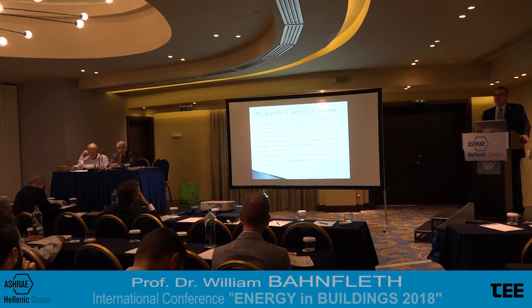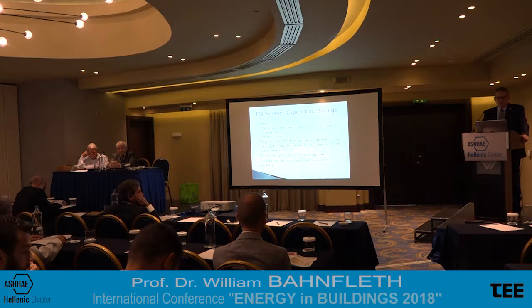On the other hand, that trades off with the cost of the thermal storage component, so I can't tell you that you can always save money with a thermal storage system compared to a non-storage system. But when you are considering something as large as a district cooling system that will probably have a stratified thermal storage tank associated with it, it's quite possible to have a lower capital cost for those systems than for one that was a direct refrigeration only system.